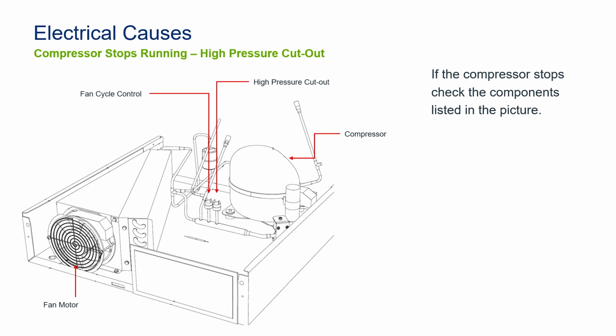Things would be true with a water-cooled system as well, but that's not electrical. That would be water supplied to a condenser, and we're talking about electrical bits. So the fan cycle control is the left switch there in the middle. Its job is to close its contacts when pressure gets to a certain point, depending on the set point of that machine. You'll find that information in your technician's handbook.